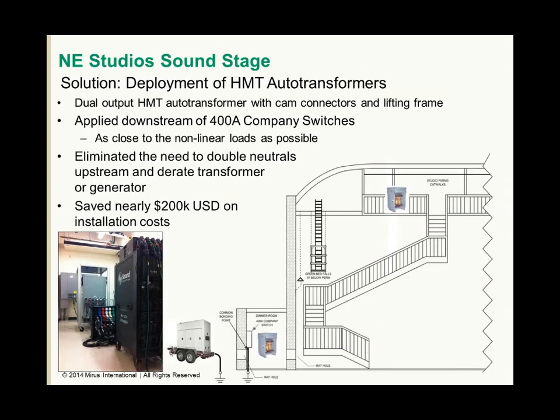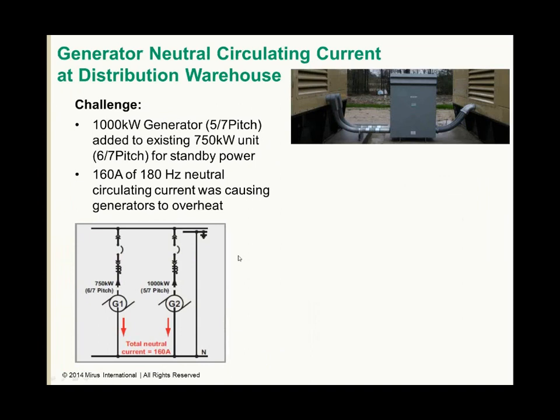The HMT auto transformers were installed in the dimming rooms and at the 400 amp company switches up on the catwalks where they drop the lighting systems. And this approach saved the facility nearly $200,000 on installed cost. The final case study to share with you today is an application where two generators of different pitch configurations were paralleled with very high levels of 180 hertz circulating current, resulting in the neutral.